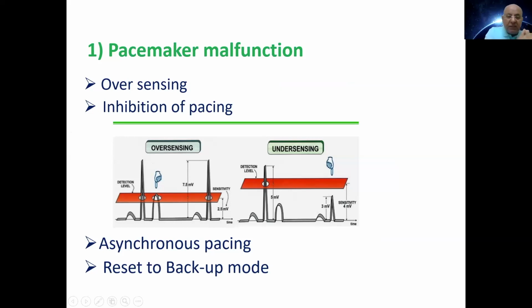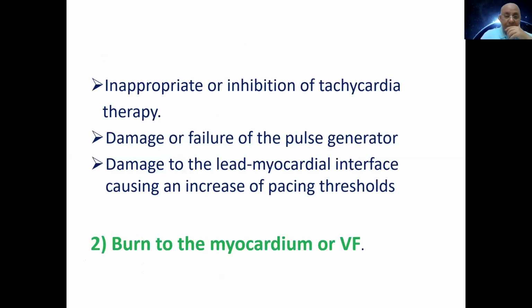Normally, the patient is physiologically adapted to a rate and rhythm interrogated over a long time. It is adapted physiologically with the interrogation by the CIED team. Every 3 months or 6 months, they change the settings to another level according to the physiological needs of the patient. Now it will bring him back to asynchronous mode, which may not be suitable for him. Or reset him to backup mode from the start, which is not fit for him at all. So all these things can happen. Also, in the ICD, there can be inappropriate inhibition of tachytherapy. It may also damage the generator or the leads themselves. It may also burn the myocardium.